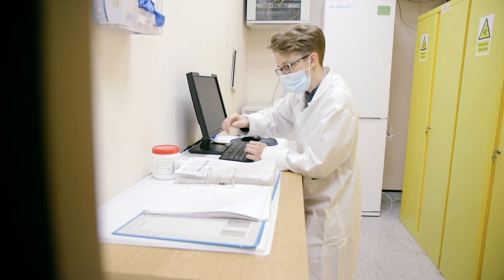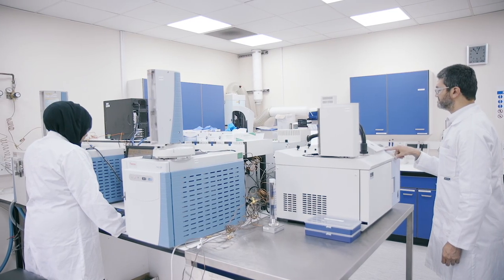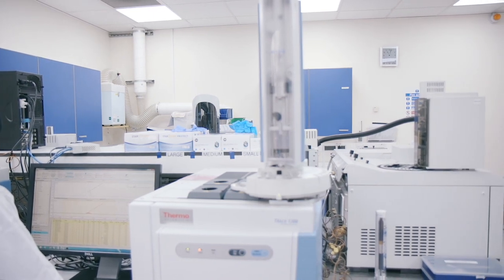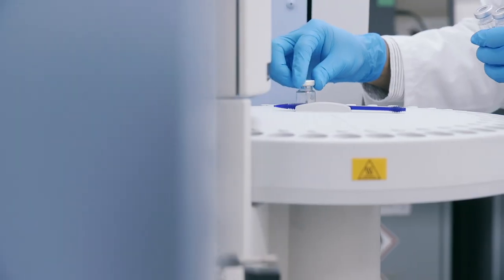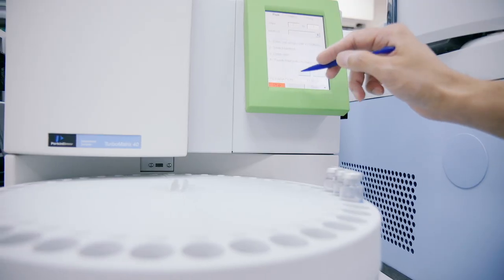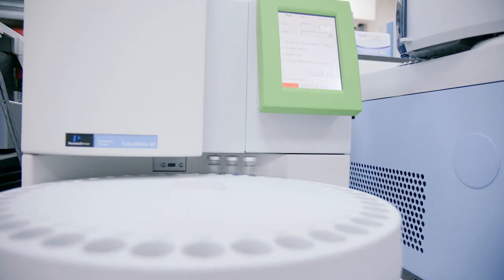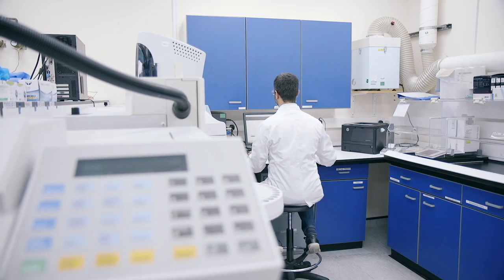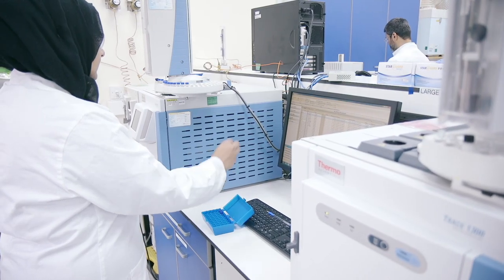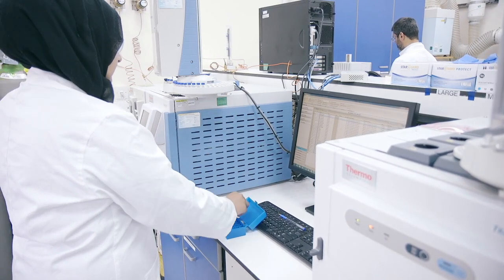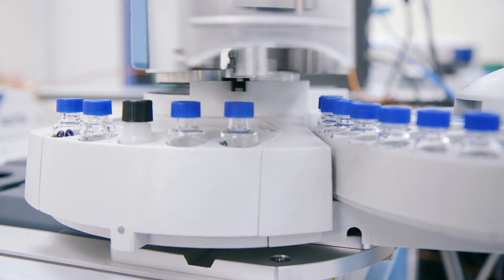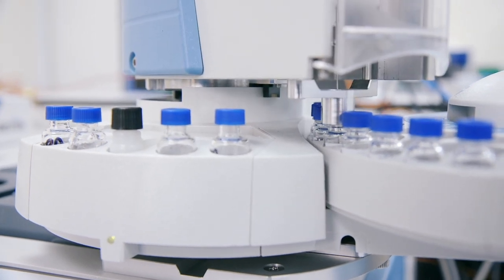Our main gas chromatography lab is segregated to ensure a low solvent atmosphere for residual solvent testing. We use two Perkin-Elmer GCs with headspace and direct liquid injection, and two Thermo Fisher GCs, one of which has ISQ-MS detection in addition to FID. We use this GC-MS for residual solvent testing, volatile organic carbon assays, and for identifying unknown volatiles, often as part of extractable and leachable studies.